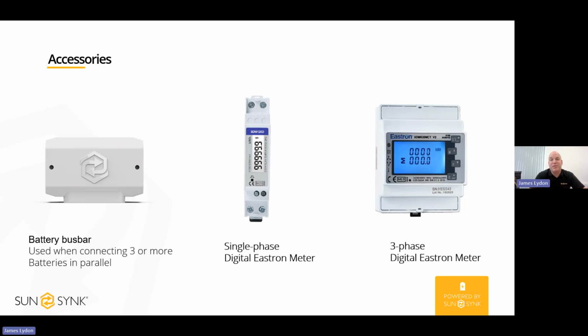Okay, so some of the accessories to go with either the Acure or the Classic range. So we've got our battery bus bar. Our batteries, which I'm going to come on to shortly, come with the cables needed. The 5 kilowatt hour batteries come with the long set of 25 mil square cables that will go from the battery to the inverter. And they also ship with the parallel lead, so you can parallel it to the battery next to it.